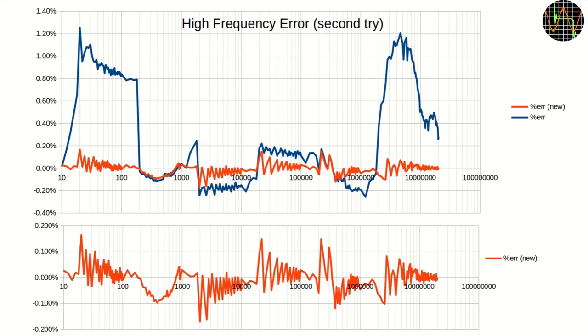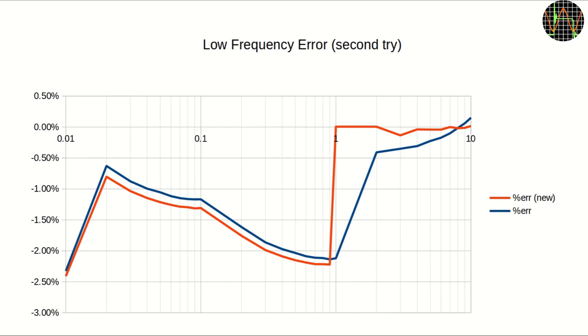And the low frequencies? I tried the same trick and from 1Hz onwards the frequencies are obviously corrected and now in the 1% tolerance spec except for a small peak at 3Hz. For the frequencies below 1Hz, the spec is 3% and obviously that jump in tolerance is needed because the correction is no longer applied. Enough of that.